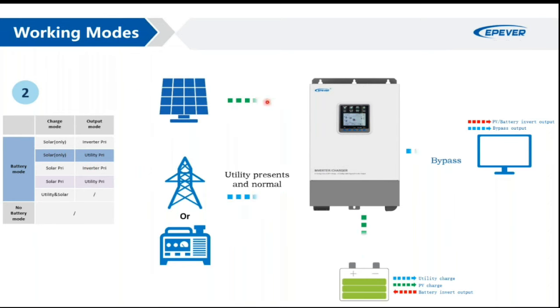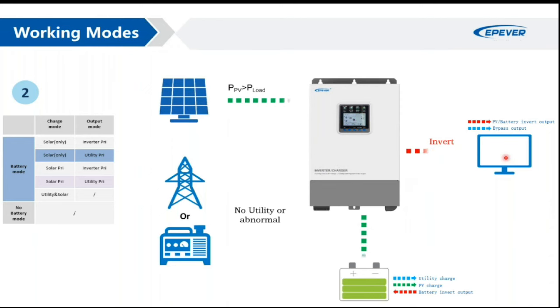In this case, if you have enough solar energy, it will be dedicated to charging the battery, and the utility will provide the power for AC consumers. If you don't have the utility, the solar panel will charge the battery and provide the output power. And if you don't have enough solar power, the battery will start to discharge, and at a certain level it will be cut off, the inverter will shut down, and the solar panel will only be able to charge the battery until it reaches LVR voltage, or low voltage reconnect voltage.